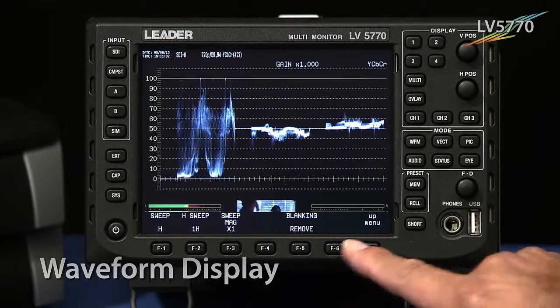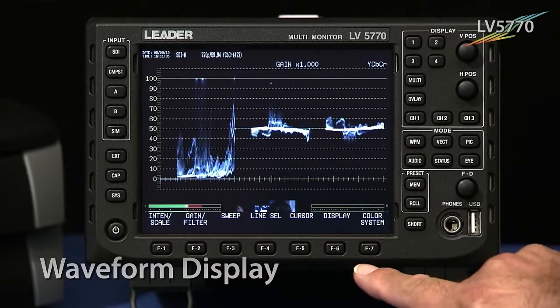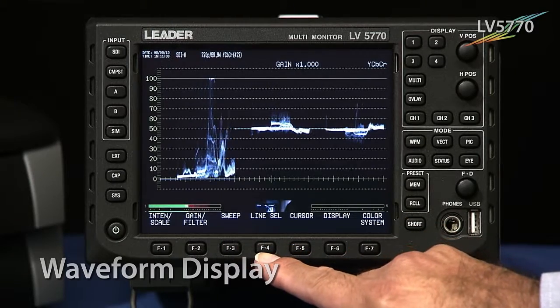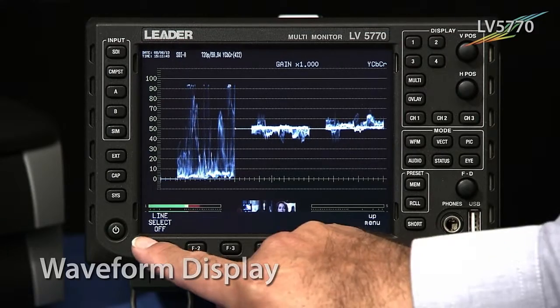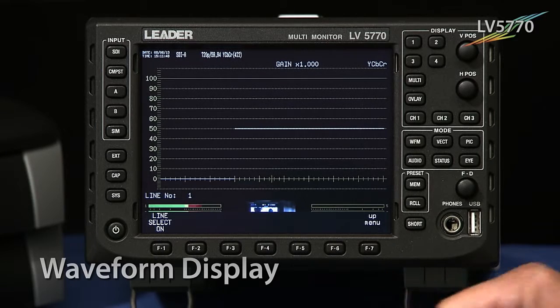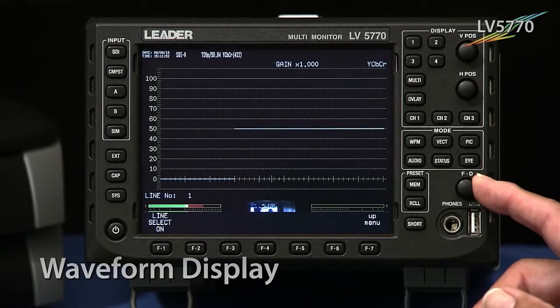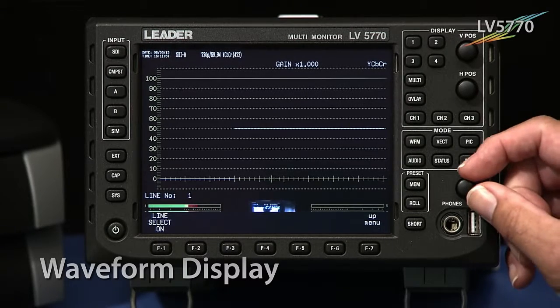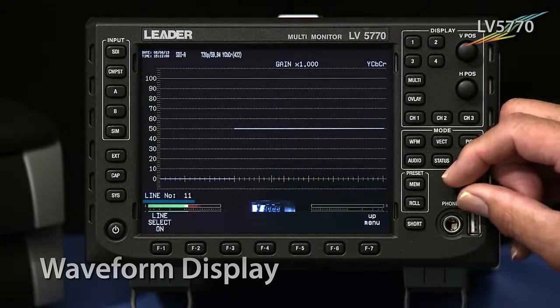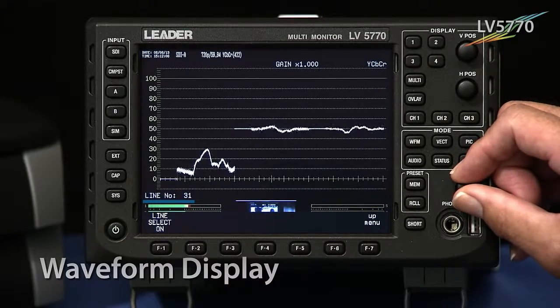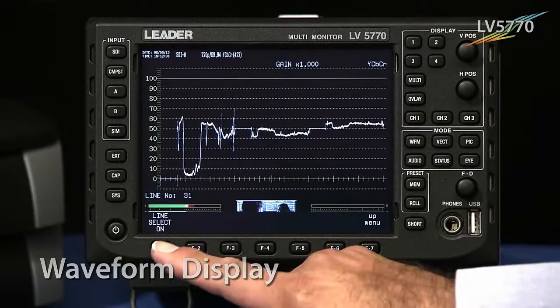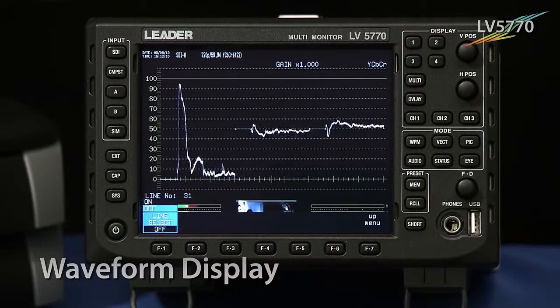We'll return that back, then hit F7 again to move up into the menu and move over to the next selection, which is F4, line select. Pressing that brings us to another menu which allows us to turn on line select. Once we've done that, the FD control — which stands for function dial — on the right-hand side will allow us to select whatever line we want to look at. By turning that, you can scroll through to whatever line of video you want to take a look at.